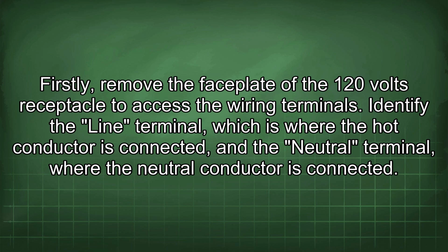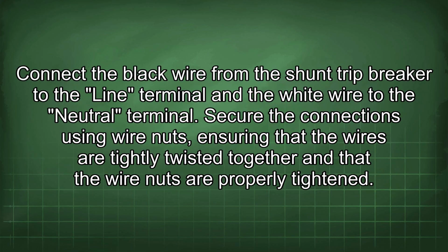Identify the line terminal, which is where the hot conductor is connected, and the neutral terminal, where the neutral conductor is connected. Connect the black wire from the shunt trip breaker to the line terminal and the white wire to the neutral terminal. Secure the connections using wire nuts, ensuring that the wires are tightly twisted together and that the wire nuts are properly tightened.